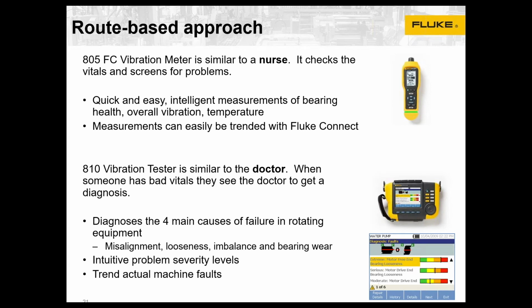The 805 FC vibration meter, kind of think of it as that nurse, going back to the healthcare analogy. It screens and it makes intelligent measurements on bearings, on overall vibration, and bearing temperature. And those measurements can easily be saved automatically in the Fluke Connect app. They can be looked at over time, or you can use that as a red flag that there's an issue here. And if the asset is critical enough, then it makes sense maybe to bring in the doctor, which is the 810 vibration tester. It actually can see the same types of problems, from an overall vibration and bearing issue standpoint. However, it can get to that root cause: misalignment, looseness, imbalance, bearing wear.